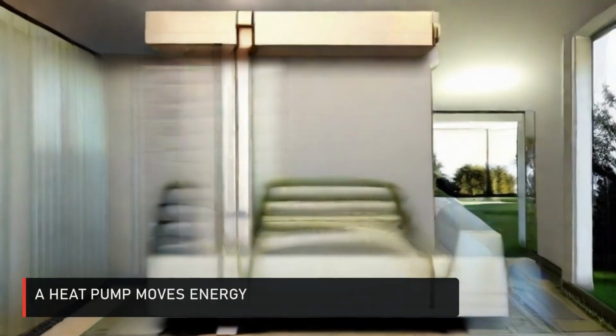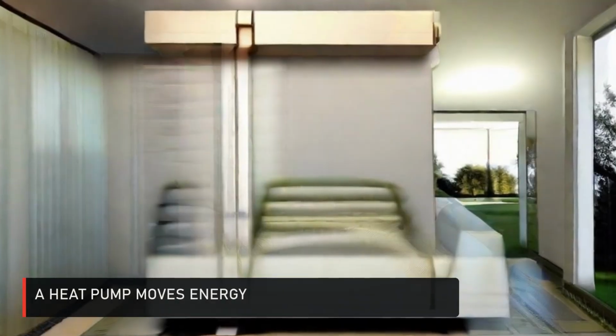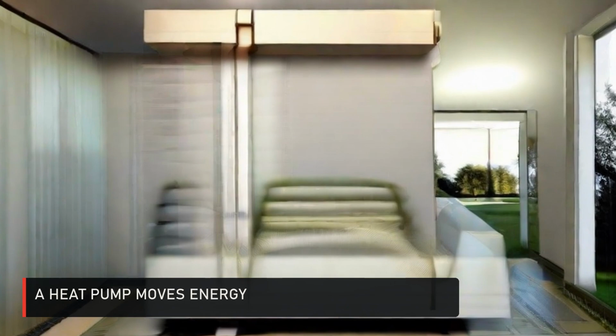A heat pump can deliver more heat to a building than the electrical energy it consumes because it moves environmental heat rather than creating all of it electrically. Electricity powers the compressor and auxiliaries while additional thermal energy is collected from air, ground, or water. That is why a coefficient of performance can be greater than 1 without violating conservation of energy. Delivered heat equals electrical input plus heat gathered from the environment. Energy is not being created from nothing.